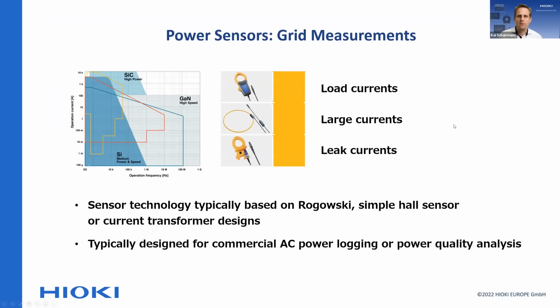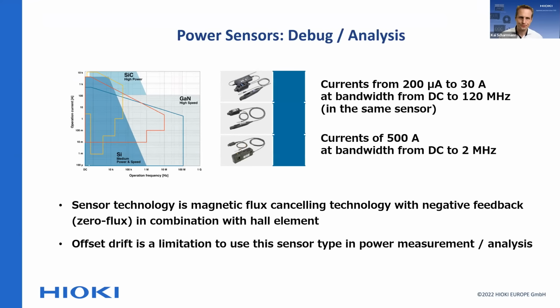Just looking at them, starting with them to get them out of the way: the typical technologies are Rogowski coils, simple Hall sensors, or simple current transformer designs. They're either made for load currents, very large currents, where the Rogowskis don't bring the required accuracy, or they're made for leak currents. Typically, you find them in AC power logging or power quality analysis, because the accuracy and flexibility there is absolutely fine.